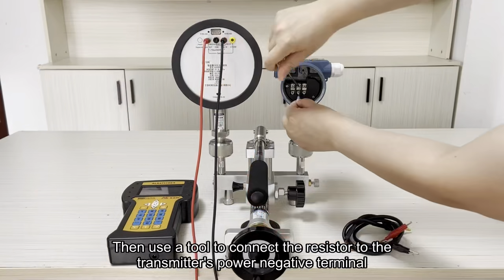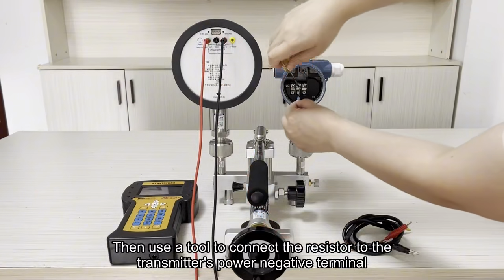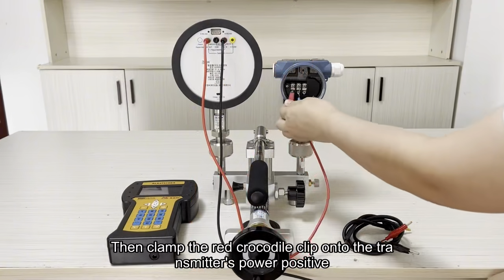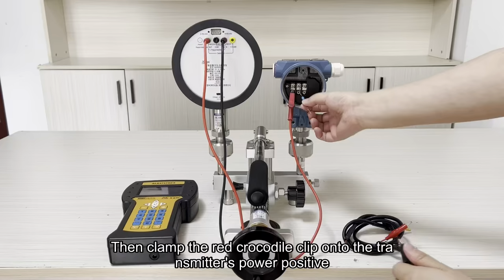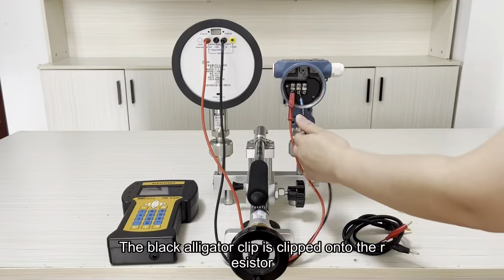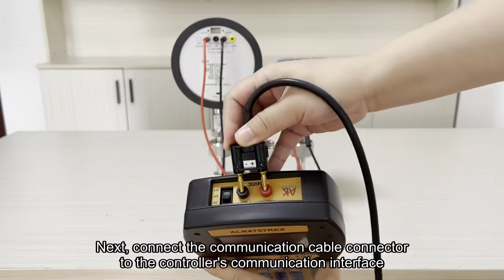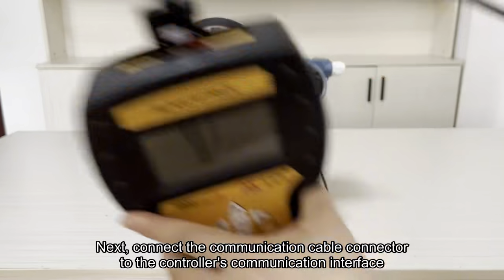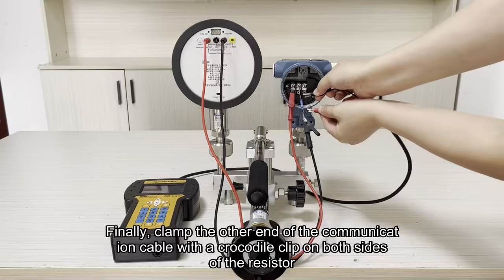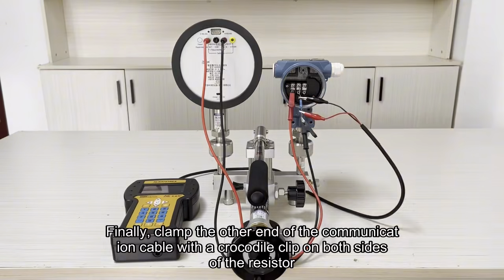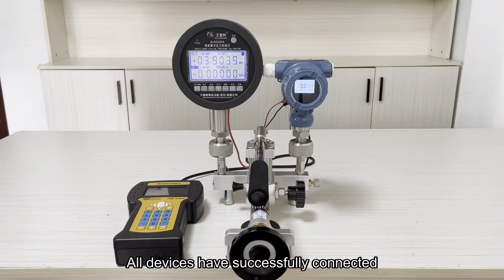Then use a tool to connect the resistor to the transmitter's power negative terminal. Then clamp the red crocodile clip onto the transmitter's power positive. The black alligator clip is clipped onto the resistor. Next, connect the communication cable connector to the controller's communication interface. Finally, clamp the other end of the communication cable with crocodile clips on both sides of the resistor. All devices have successfully connected.